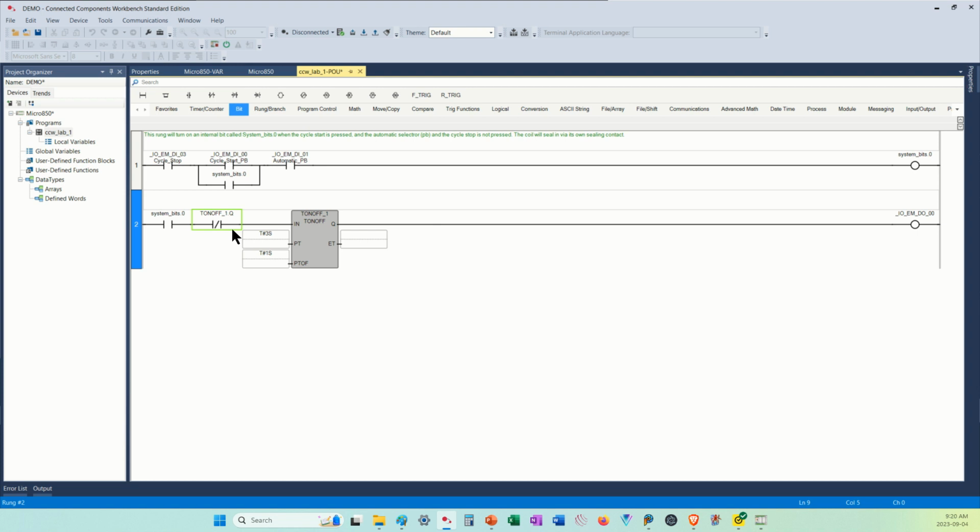Now you're probably saying, well, why? You've got a program on time, you've got a program off time, why would you want that? The way a TONOFF works, it actually is two different instructions. It's an on-delay timer and an off-delay timer. And off-delay timers need to be kick-started.